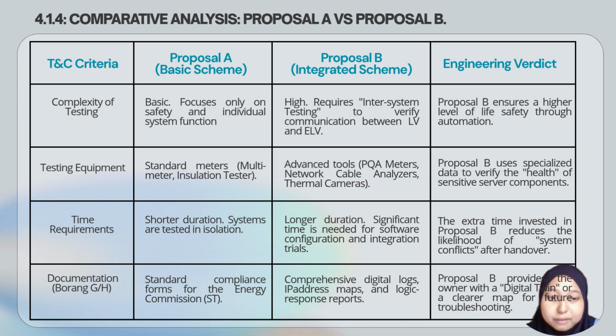Next, let's talk about the comparative analysis for Proposal A versus Proposal B. In terms of the criteria for complexity of testing, Proposal A is basic and focuses only on safety and individual system function. But Proposal B is high, requiring inter-system testing to verify communication between LV and ELV. For the engineering verdict, Proposal B ensures a higher level of life safety through automation. Next is testing equipment. Proposal A uses standard meters, which are a multimeter and insulation tester. And Proposal B uses advanced tools: PQ meters, network cable analyzers, and thermal cameras. For the engineering verdict, Proposal B uses specialized data to verify the health of sensitive server components.